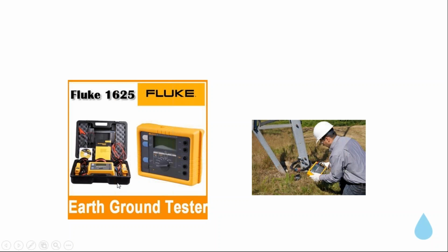There's a couple on the market—this is the Fluke 1625. You put a bunch of electrodes in the ground. There's quite a bit of cable here, about 50 feet, with little stakes. You stake them all in the ground around the site, and this box sends out a surge. Then you can connect this to the grounding system you have and see how well it dissipates the surge coming from the box.